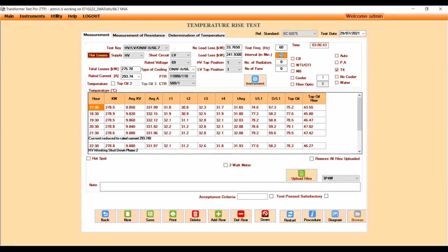This is with 60 minutes set as the interval. The moment you set it like this, in the table and the center below, every 60 minutes the data for kilowatts, average kV, average ampere, and all the temperatures are measured. You can see in the last column, that is the top oil temperature rise.